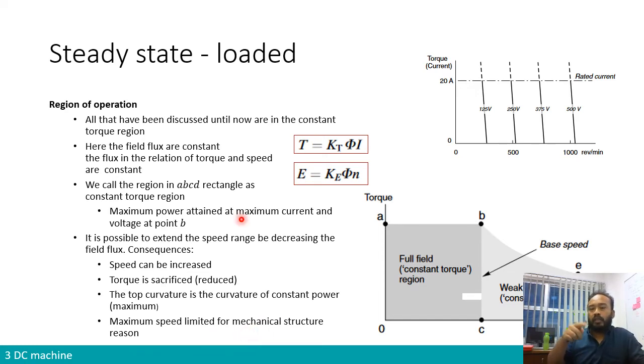Why? Because when you start rotating very quickly, you have the centrifugal force. And when you have a centrifugal force inside your armature, your armature winding will be accelerating toward the external surface, and it may damage your rotor structure. So that's what we call flux weakening: diminishing or reducing the flux so that we can increase in speed.